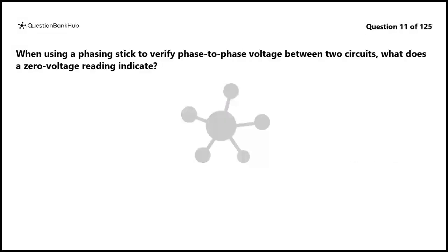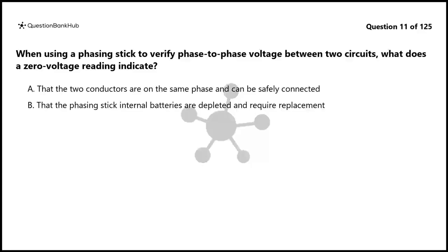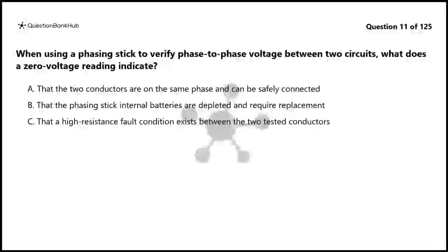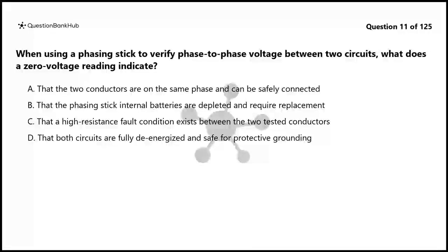Question 11. When using a phasing stick to verify phase-to-phase voltage between two circuits, what does a zero voltage reading indicate? A. That the two conductors are on the same phase and can be safely connected. B. That the phasing stick internal batteries are depleted and require replacement. C. That a high-resistance fault condition exists between the two tested conductors. D. That both circuits are fully de-energized and safe for protective grounding.